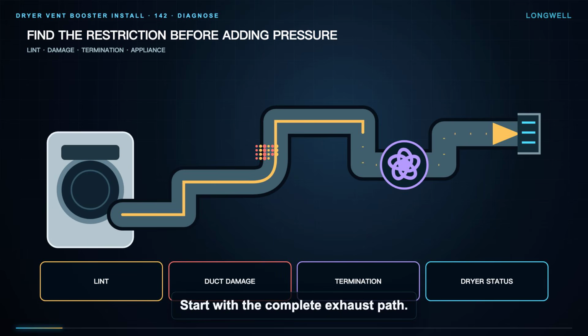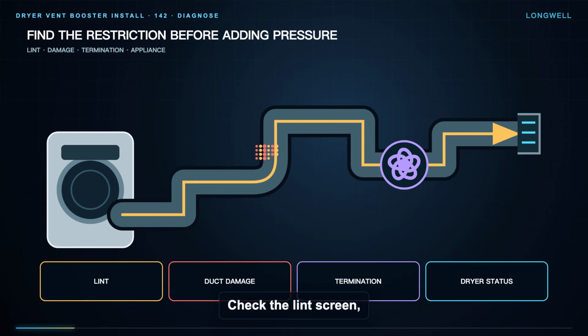Start with the complete exhaust path. Stop the dryer, follow the applicable isolation procedure, and inspect only within your competence. Check the lint screen, accessible duct, joints, supports, and outdoor termination for restriction, damage, separation, or trapped lint. Confirm that the dryer itself is operating as intended. If the path is blocked or damaged, correct that condition first. A booster must never be presented as a substitute for cleaning, repair, or appliance service.